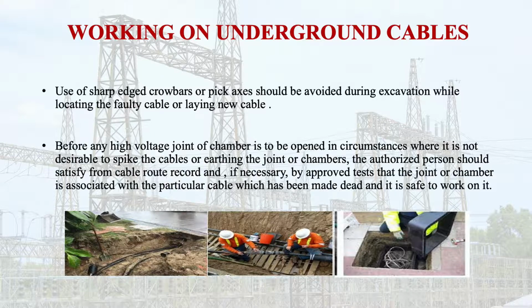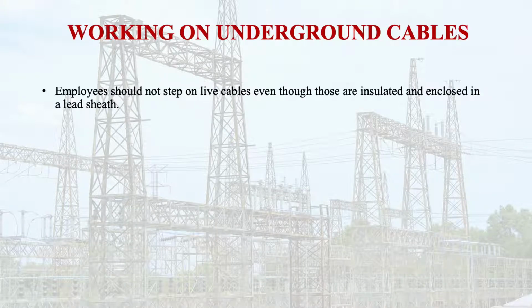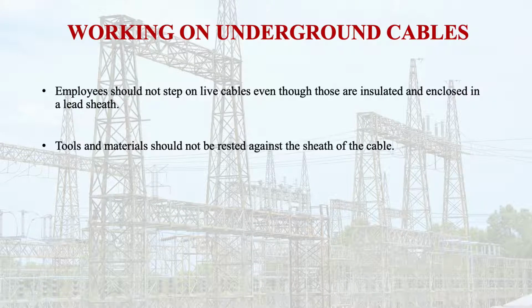Before any high voltage joint chamber is to be opened, in circumstances where it is not desired to spike the cables or earth the joint or chamber, the authorized person should satisfy himself from the cable route record, and if necessary by approved test, that the joint or the chamber is associated with the particular cable which has been made dead and it is safe to work on it. Employees should not step on live cables even though those are insulated and enclosed in lead sheath. Tools and materials should not be rested against the sheath of the cable. It may also cause some danger.